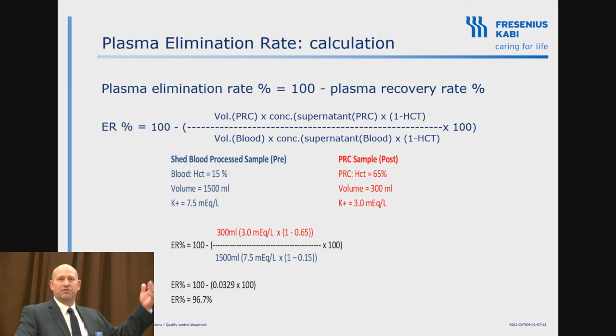Another problem I see in quality control is people using the iStat or devices like the iStat. It's a good device, but it uses conductivity to measure hematocrit in a whole blood sample. This is not a whole blood sample. This is a sample with very little plasma component. Plasma is the conductive portion of this algorithm they use, and the red cells insulate more. So the higher the hematocrit, the more the results are skewed. That's why they have that number. I don't know, a lot of people use iStat here. Anybody? So you put that number in the CPB number to get a little fudge factor, because when you go on pump, it dilutes it a little. So send it to the lab. You're going to get a better number and more accurate.